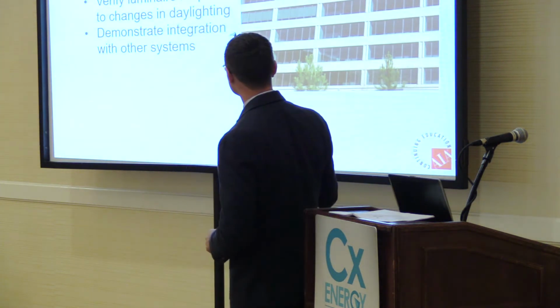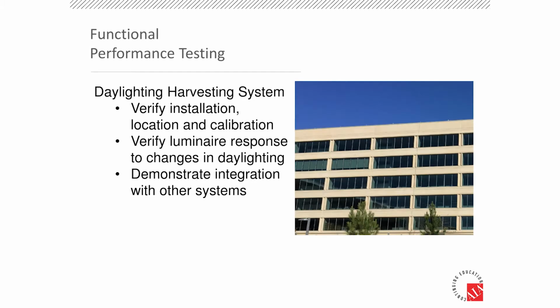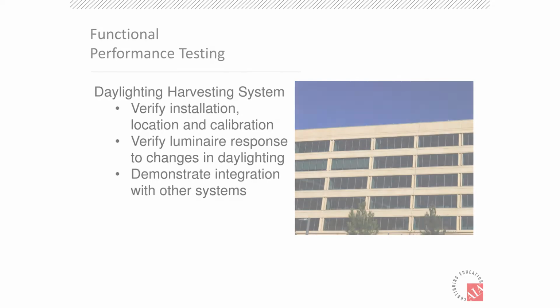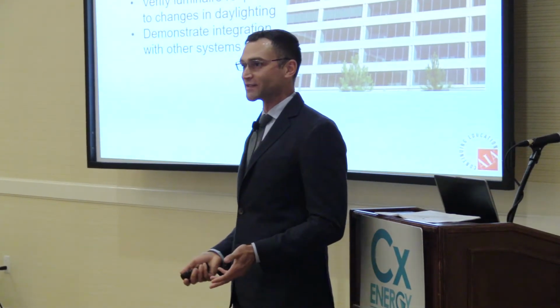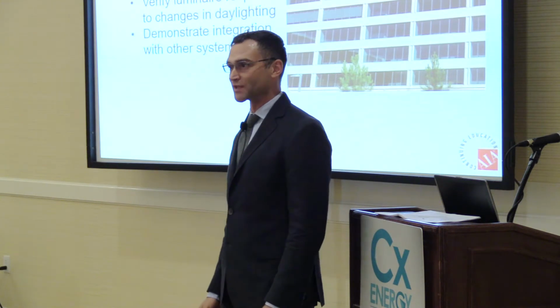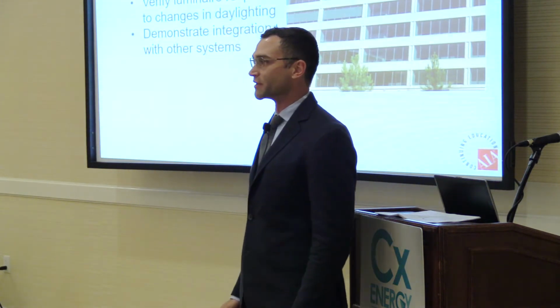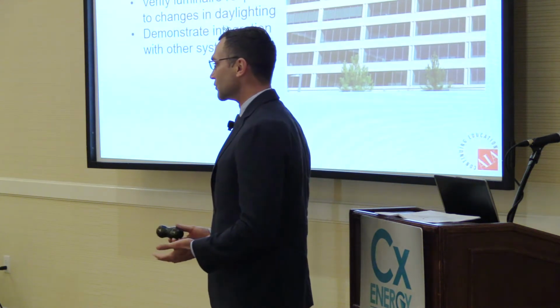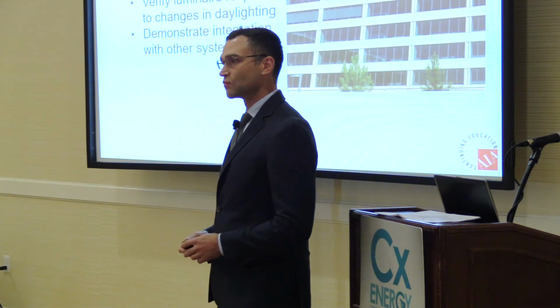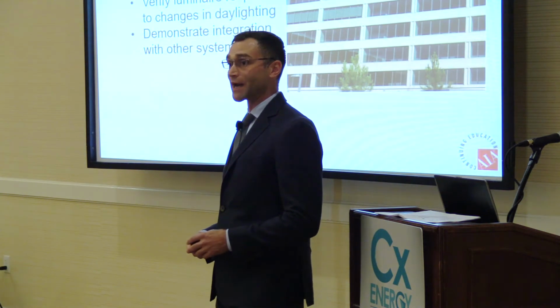This picture, I included intentionally. This is more of just a quick story. You can walk outside a building with power shades fairly easily and see what's scheduled properly and what's not. If the shades are incorporated into daylight harvesting photocells, you can tell what's happening and what's not.